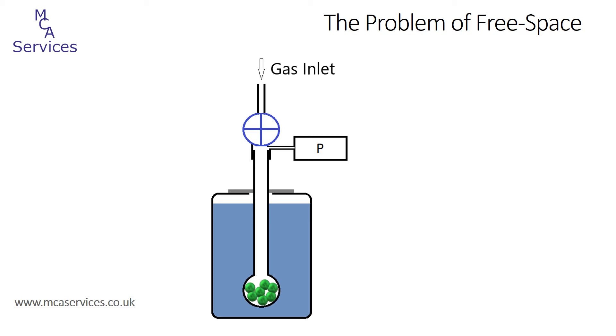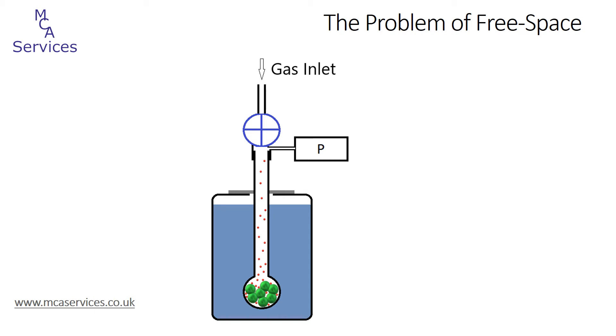The blue circle at the top represents a valve which opens when we need to dose adsorbate to the tube. If we admit adsorbate gas to the analysis tube — shown here as the red dots — we find that at equilibrium some atoms will be adsorbed onto the sample, while others will remain within the analysis tube not adsorbed to the sample. The portion of the tube that does not contain sample is called the free space. The transducer measures the pressure within the entire tube, which is converted to a volume within the entire tube for each adsorption relative pressure of the isotherm. So to find the volume adsorbed to the sample, we must subtract the free space volume from the total volume of adsorbate dosed into the tube at every relative pressure analyzed.